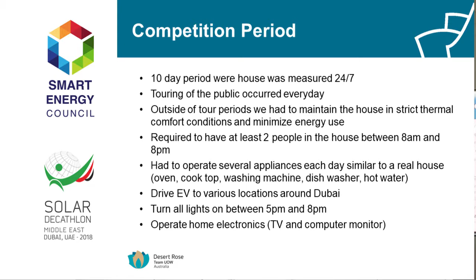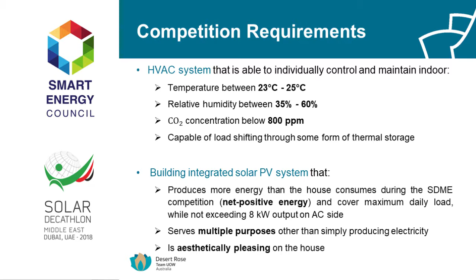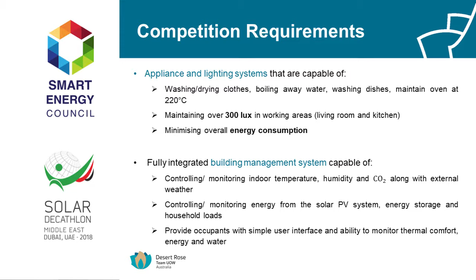For the air conditioning system, we had to maintain temperature between 23 and 25 degrees Celsius, just a 2-degree band - probably better than most fridges can do. Relative humidity had to stay between 35 and 60%, and CO2 below 800 parts per million. We needed to be net positive energy, and they also wanted to see solar PV that served multiple purposes. We had to wash and dry towels, boil away water, wash dishes in our dishwasher, and maintain the oven at 220 degrees for an hour - all these different things to make sure the house operated as it should.